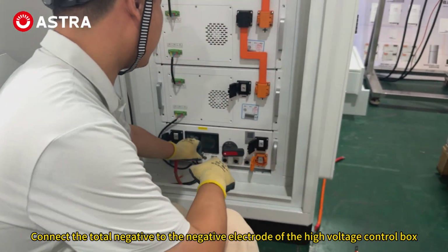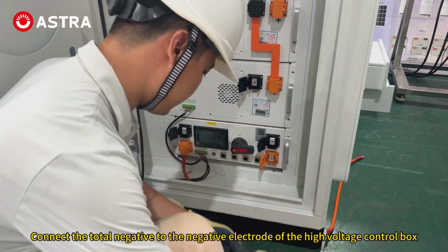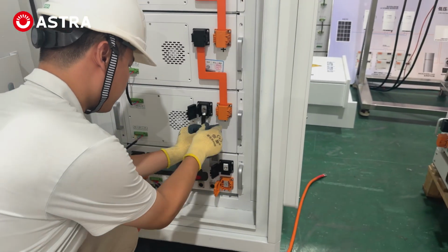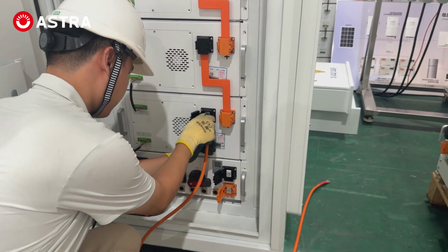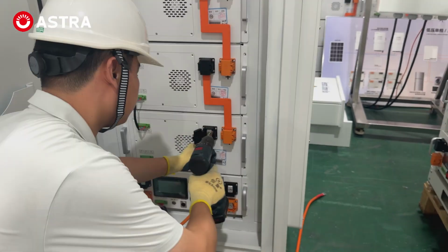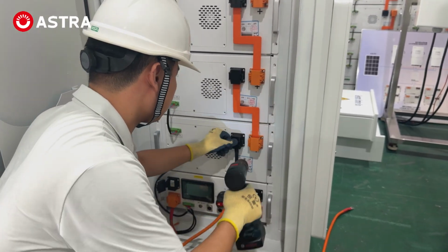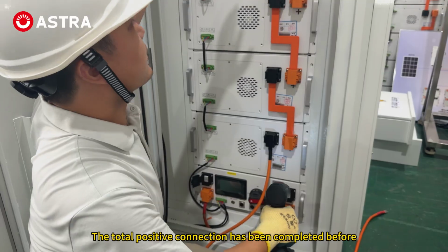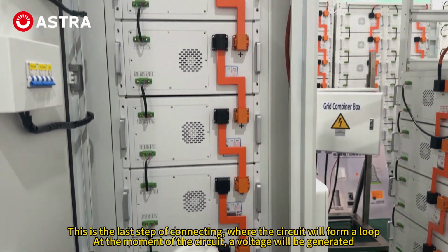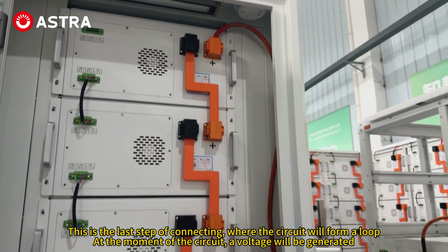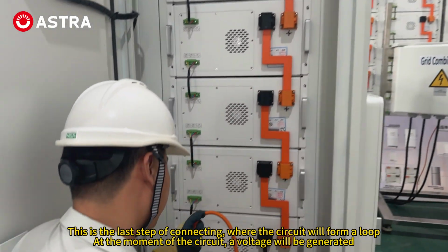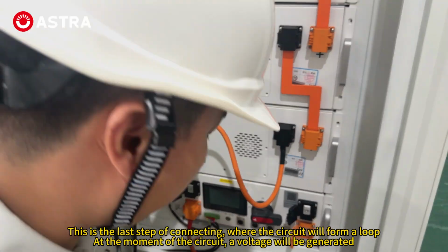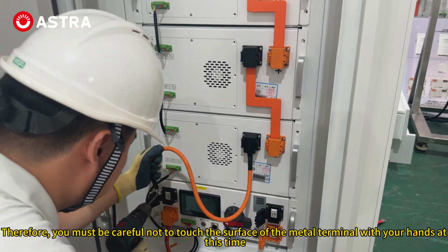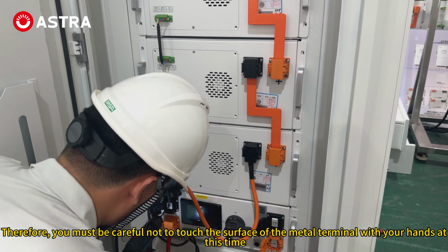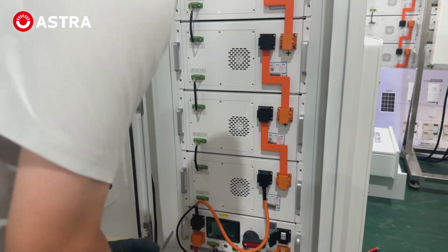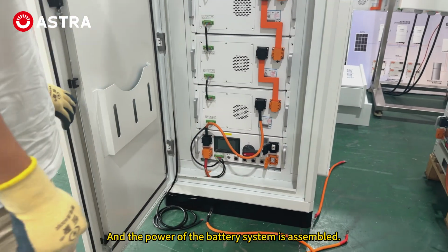Connect the total negative to the negative electrode of the high voltage control box. The total positive connection has been completed before. This is the last step of connecting, where the circuit will form a loop. At the moment of the circuit, a voltage will be generated. Therefore, you must be careful not to touch the surface of the metal terminal with your hands at this time. And the power of the battery system is assembled.